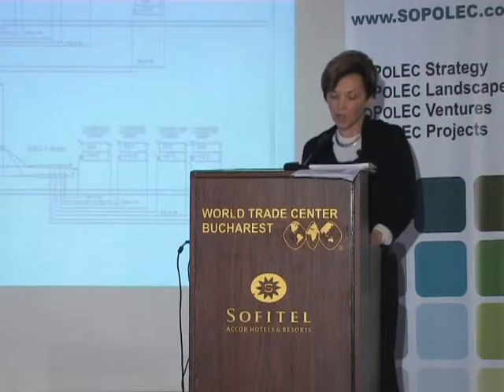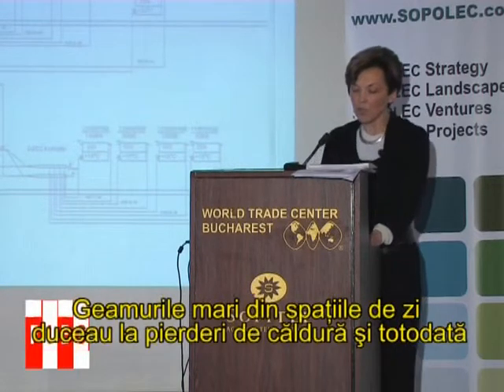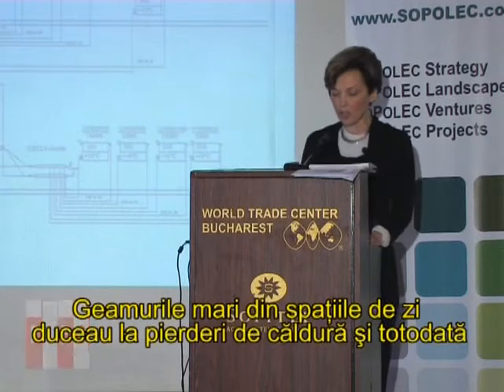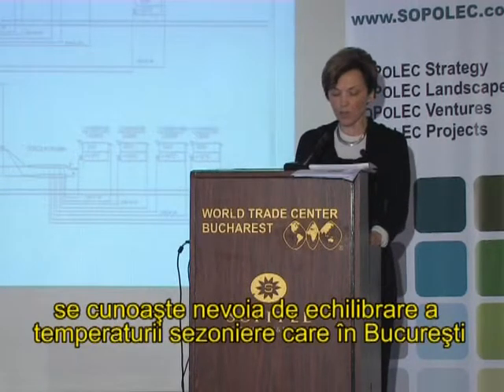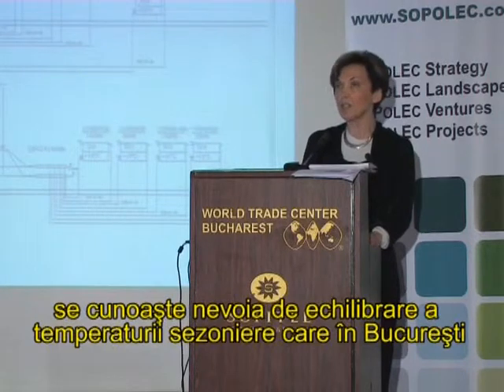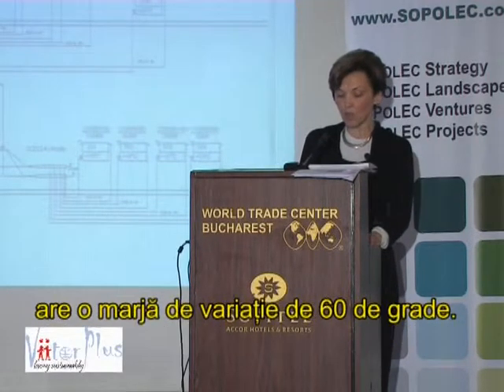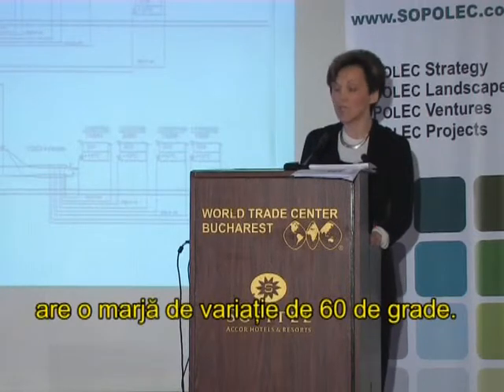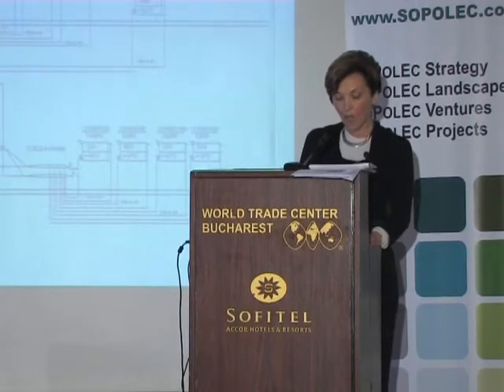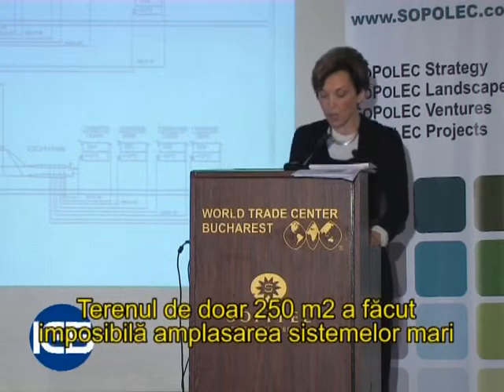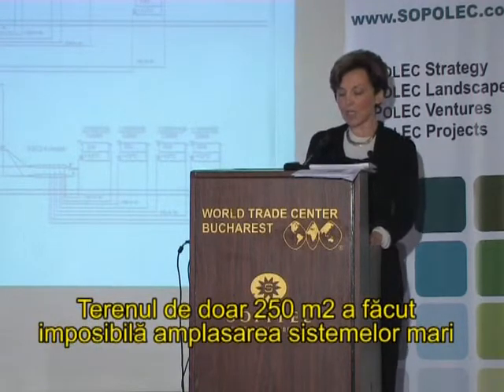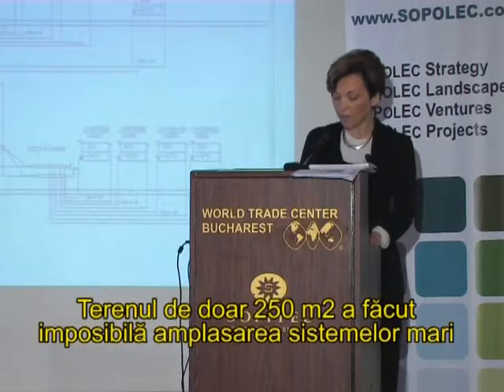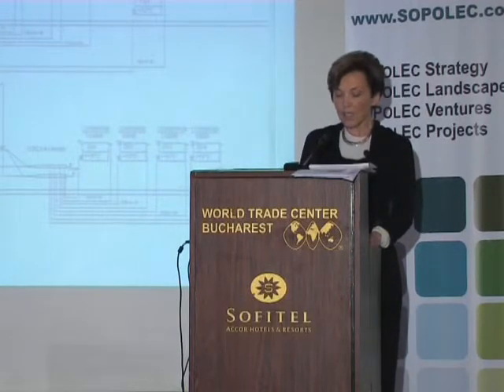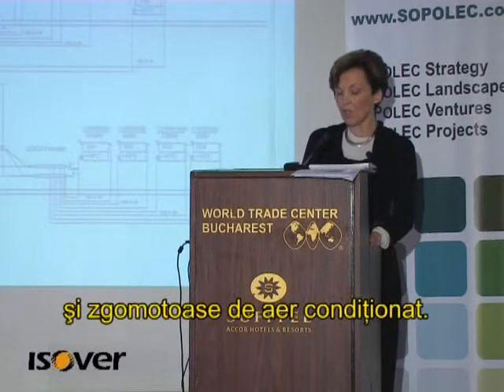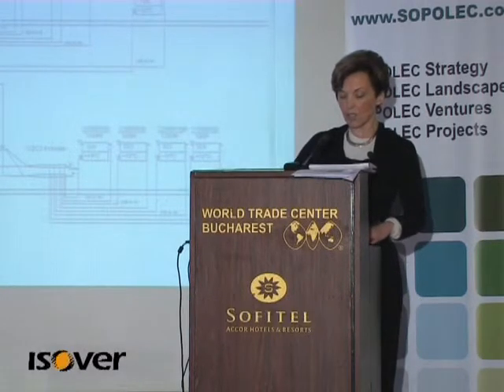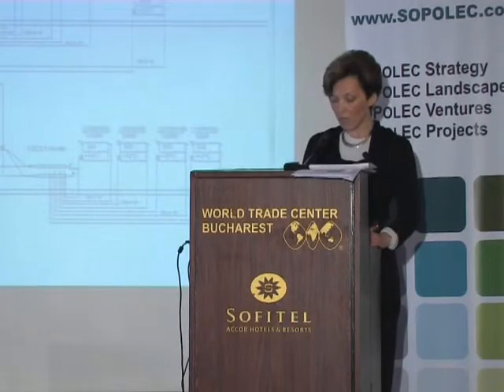The facade structure, with large windows for the main rooms, leads to important thermal losses and needs a long-life system for internal climatization, knowing that the temperature difference between summer and winter in Romania is about 60 Celsius degrees. The small terrain area, only 250 square meters, dedicated to garden wherever possible, made the settlement of usual large and noisy air conditioning equipment like chillers undesirable.